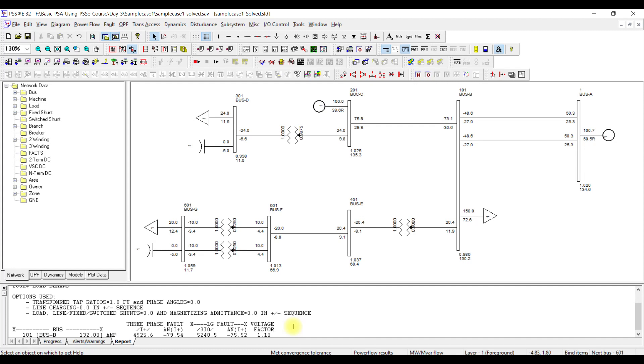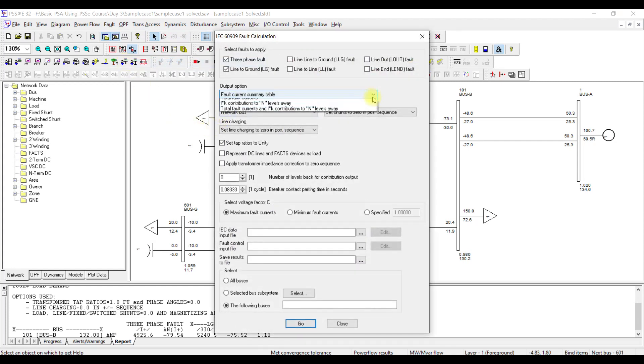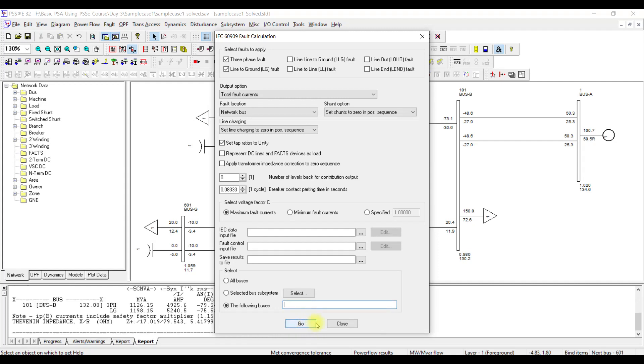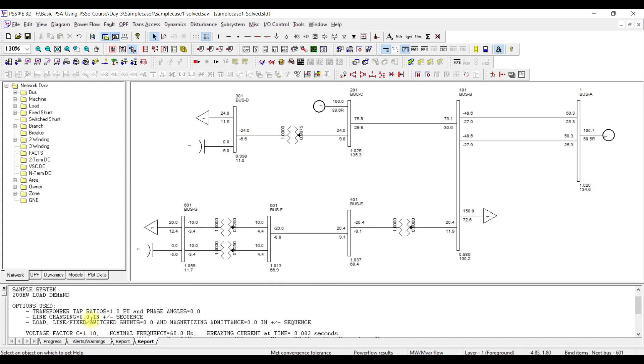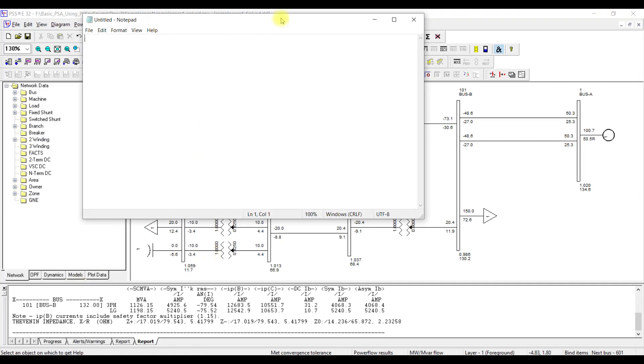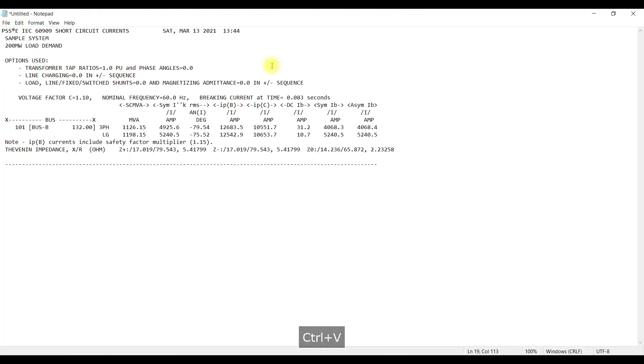Now let us perform the same analysis again with a different output option. Going back to Fault, IEC 60909, instead of summary let me select total fault current so I can see all the different currents — the asymmetrical, the breaking current, the DC current, and the AC current. I will use bus 101 again and press Go. This time I get a more detailed result. Let me copy this result, right-click, copy, and paste it into Notepad so we can study it in detail.